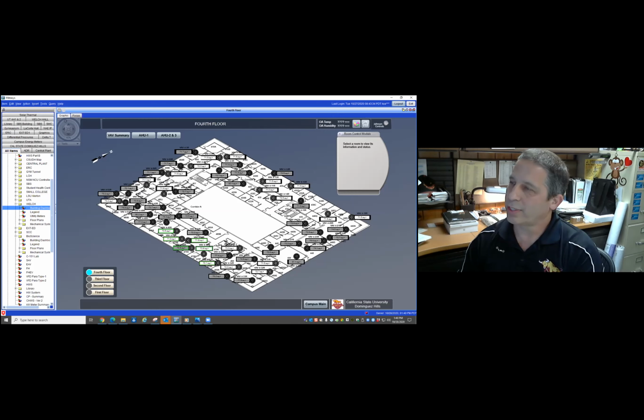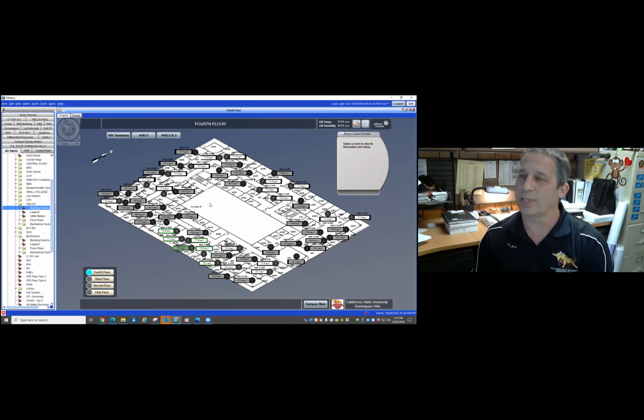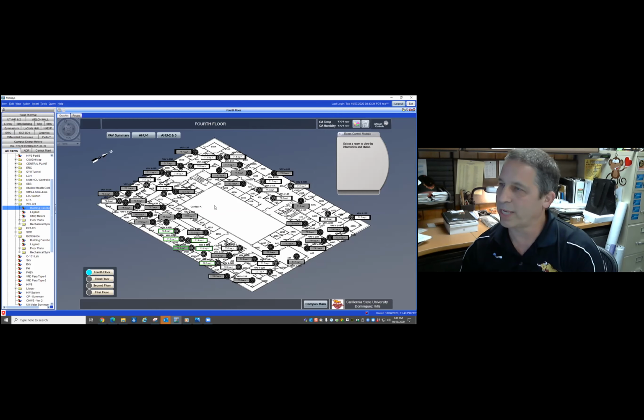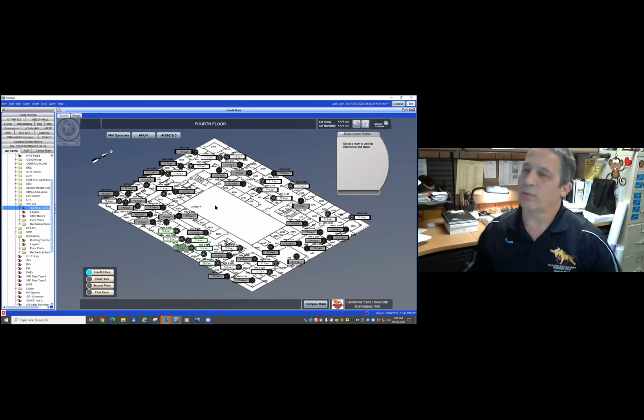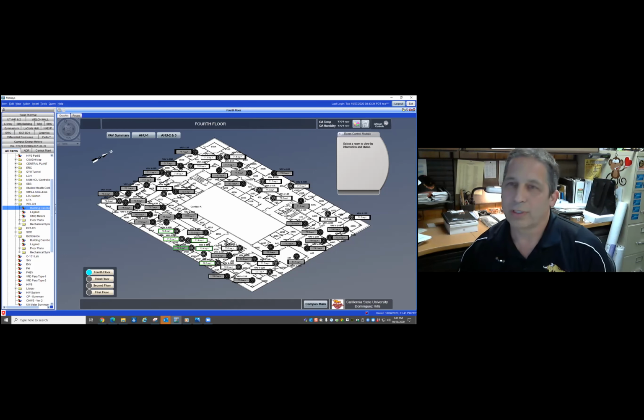It's interesting to see that on the north side of the building, we're not really doing any cooling over there, but the rooms are maintaining 71 or so, 72 degrees without any heating or cooling. Whereas on the south side of the building, where we're getting more sun, the zones that don't have any people in them get to 74, 77, 80, 76, 77. That plays a big part in how we control those zones, how far out of whack do we let them get before we make sure we cool them down again so that when people come in, it's not too hot. With COVID, it's just a balancing act right now because we don't want to cool off the entire building when there's only a handful of people here and there.